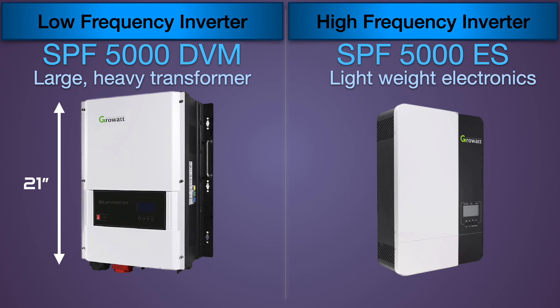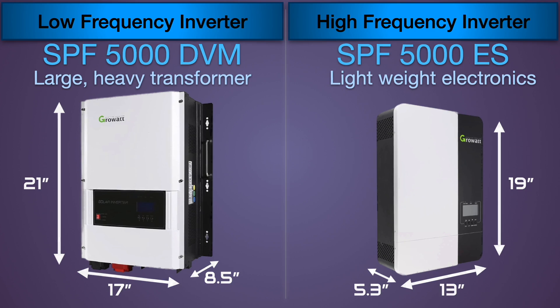Now, because this has a big heavy transformer in it, it's going to be larger and heavier. So we're going to compare this: 21 inches tall on the high frequency, it's only 19. We've got 17 inches wide on the low frequency versus 13 inches, 8.5 inches deep versus 5.3. So the low frequency is about 20 to 25% larger in all dimensions.